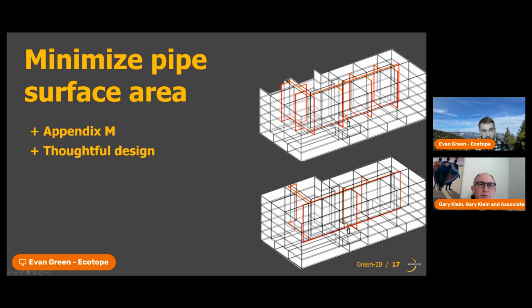But if you were able to work early on with the architect and thoughtfully plan your pipes, you could arrange these units and the pipes that serve them to allow one pipe to serve 2 units. So we're cutting the number of risers we have in half, which is going to greatly reduce the amount of surface area that serves as a means of heat transfer out of the hot water in these pipes.